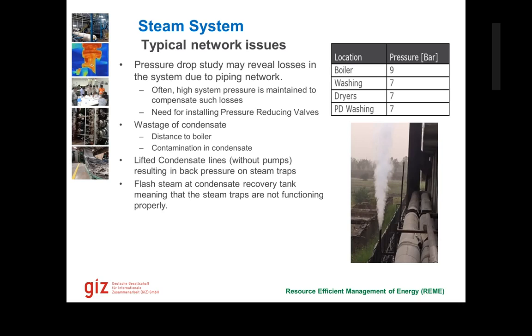What happens is that condensing takes place, it puts back pressure on the steam traps, and in turn the steam traps stop working. And then at the condensate recovery tank, we see this kind of flash steam. You can see this is a very, very long plume of flash steam going out from the condensate recovery tank, which shows that the steam traps are not working.